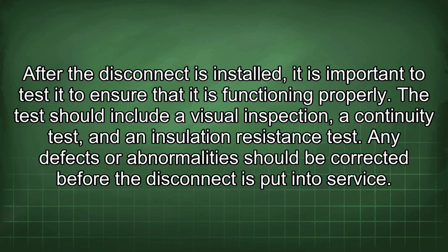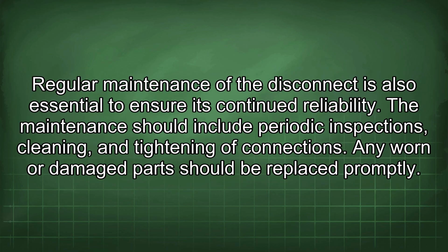After the disconnect is installed, it is important to test it to ensure that it is functioning properly. The test should include a visual inspection, a continuity test, and an insulation resistance test. Any defects or abnormalities should be corrected before the disconnect is put into service. Regular maintenance of the disconnect is also essential to ensure its continued reliability. The maintenance should include periodic inspections, cleaning, and tightening of connections. Any worn or damaged part should be replaced promptly.